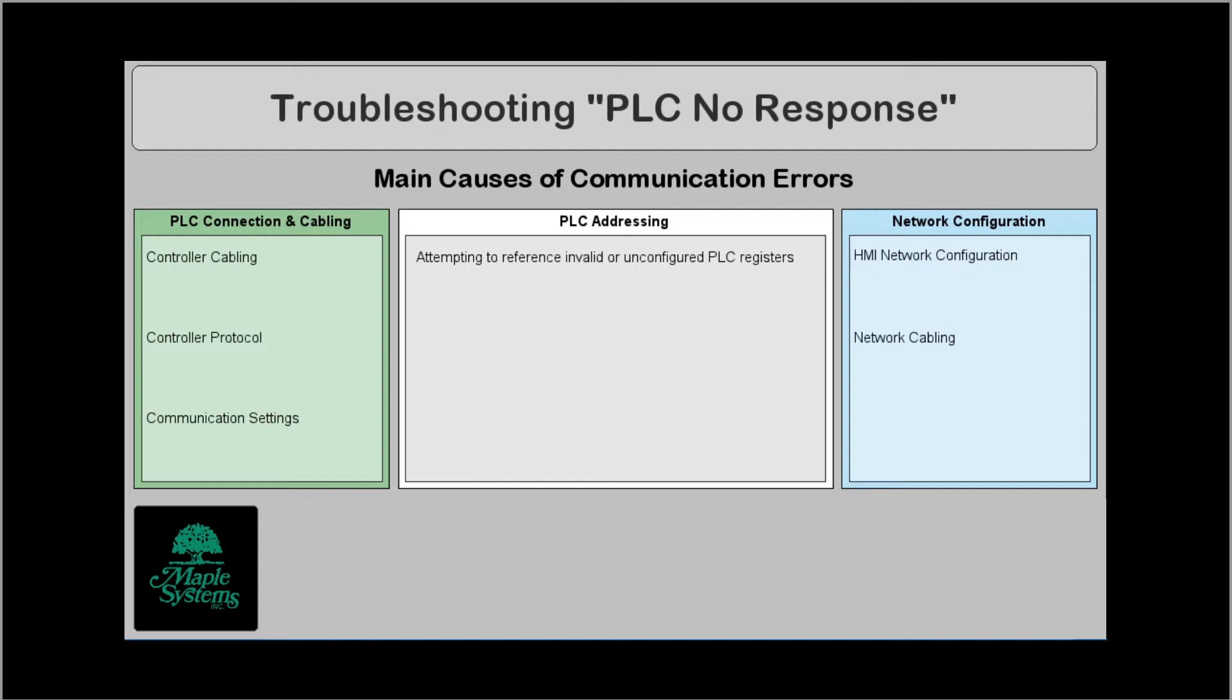For example the cable that you're using to communicate between the HMI and PLC may be wired incorrectly. Maybe your protocol you've selected is not correct for the given controller that you're using. The communication settings you've applied in EB Pro may not match what has been applied in the PLC itself. You may be attempting to reference invalid or unconfigured registers in the PLC. Maybe your HMI IP address or subnet is not set up properly to allow for it to talk with the PLC or maybe a network cable has become unplugged. These are all common reasons for the PLC no response error message.